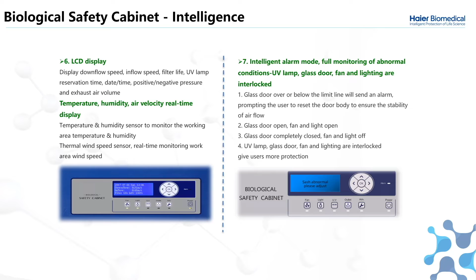There's an intelligent alarm mode which allows you to monitor abnormal conditions and alerts you to change the UV lamp, the glass door, fan and lighting, which are also interlocked. The glass door and the over/under limit can also be controlled, and it can display any sash abnormal readings.